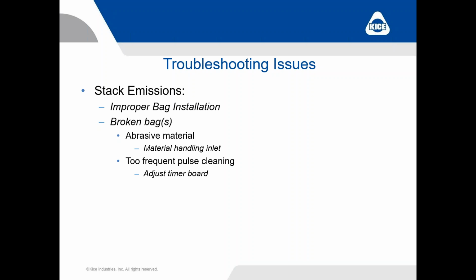But also bag installation. I don't know how many times I've taken phone calls from people that say, you know, we've installed a new set of filter bags on Monday, and here it is Friday, we're shooting dust all over the parking lot. What's the deal? Well, bag installation is just as important as anything else, and a lot of times it's the simple, easy things that are the right answer. So bag installation, we want to make sure we know what we're doing and we're doing it correctly.